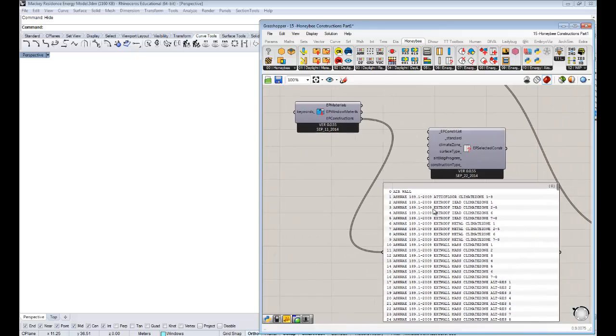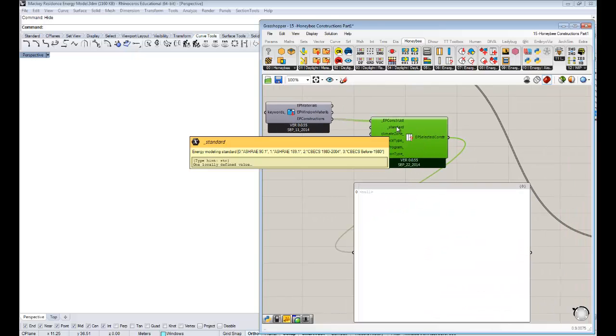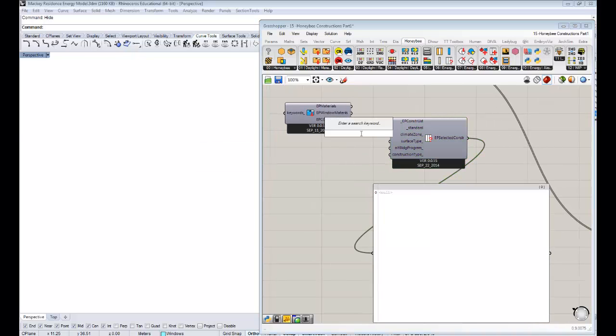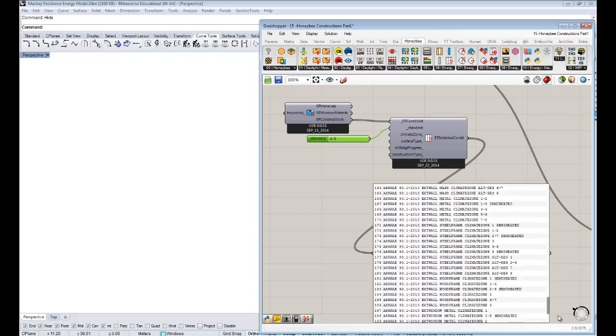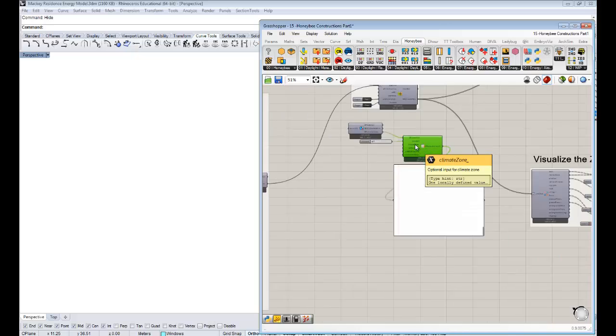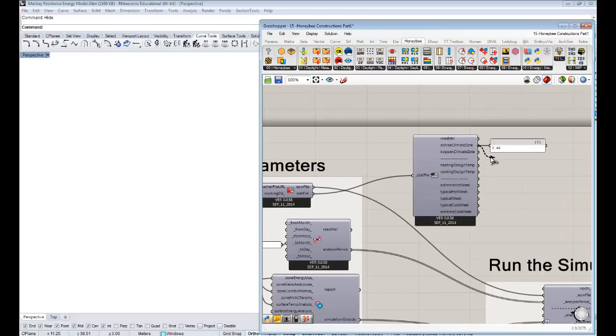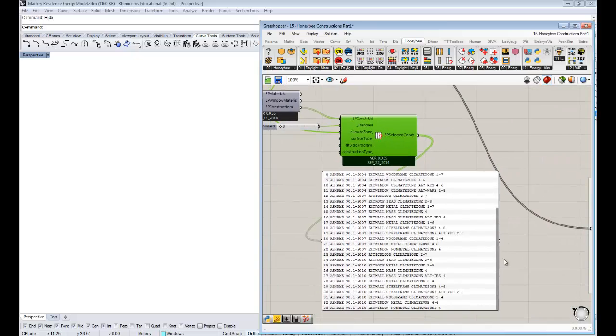You can select a certain standard you want — 0 is ASHRAE 90.1 and 1 is ASHRAE 189. ASHRAE 90.1 is one that a lot of cities use for their minimum insulation requirements. I'll type 0 in there and get all constructions for ASHRAE 90.1. You can also narrow it down by climate zone — and you don't even need to type it manually. You can take the ASHRAE climate zone output from the import stat file component and plug it directly in. Now it gives all constructions relating to climate zone 4A.